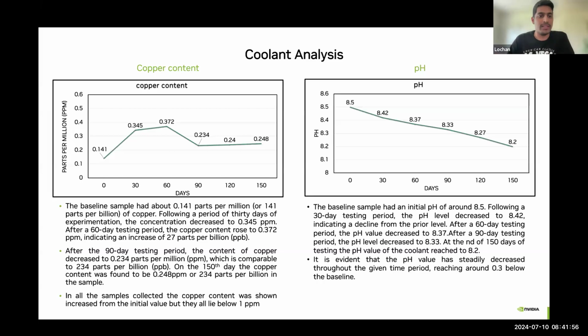As Pradeep mentioned earlier, in the loop we were only using copper. The main source of copper was the cold plate itself. All the other parts we were using, the fittings, the reservoir and the heat exchanger, were all made from stainless steel, which eliminates them as a copper source. From this we can see that any variation in copper in the coolant would be from the cold plate itself. So overall, for the 150 days of testing, the copper content level was below 1 ppm.